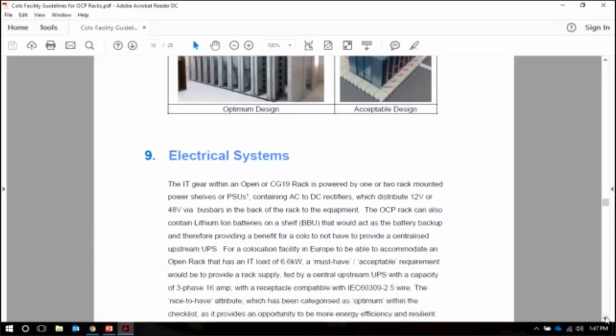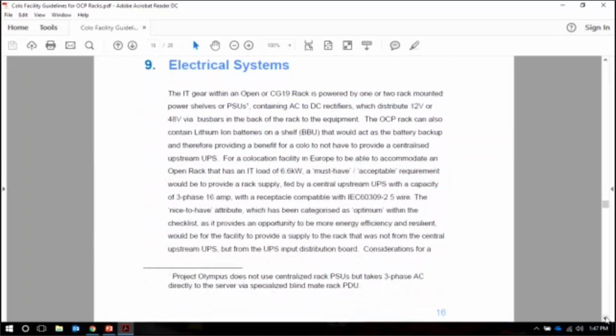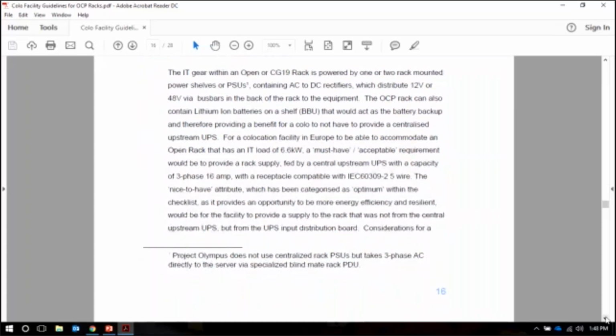The electrical system is pretty straightforward, except that for all three variants you're going to want to bring three-phase power to the rack, because most of the rectifier systems take three phases in. So a three-phase 32 amp feed is going to be typical - you can get away with 16 amp, but 32 amp would be optimal. In Europe and the US it would be 20 amps or maybe 40 amps. This isn't updated for the US, but the special thing in the US would be 277/480 right to the rack versus 208/120. You could also do the 415/240 setup.